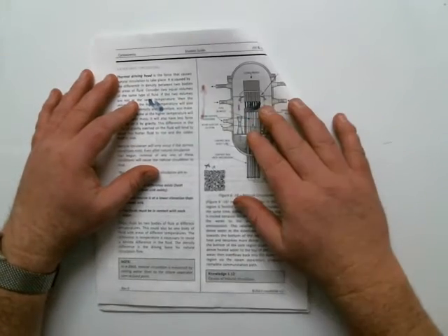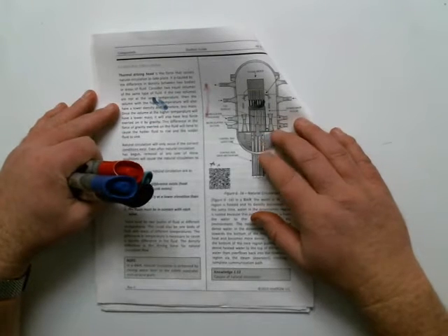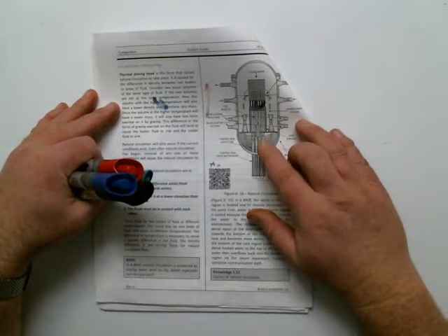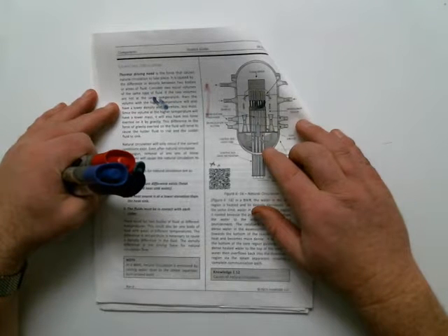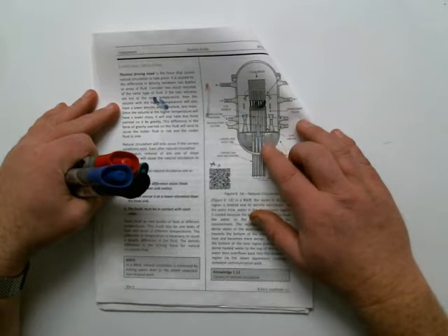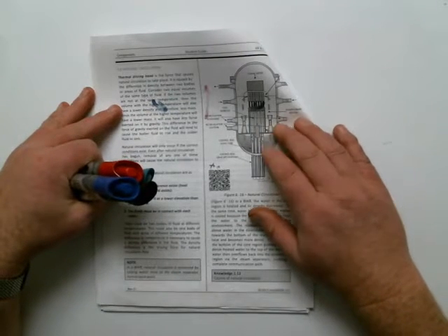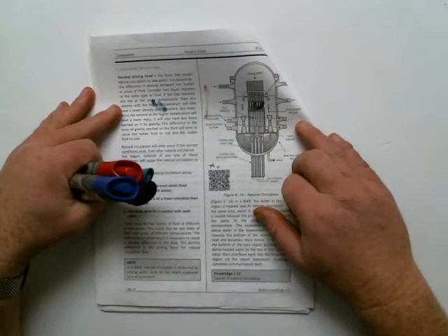All right, now we're talking about natural circulation. This is an important topic for all boiling water reactor operators to know, understand, and truly appreciate, because there will come a time in your career where you're relying on this to remove decay heat, specifically on a loss of offsite power, potentially for a moment while you're recovering forced flow.